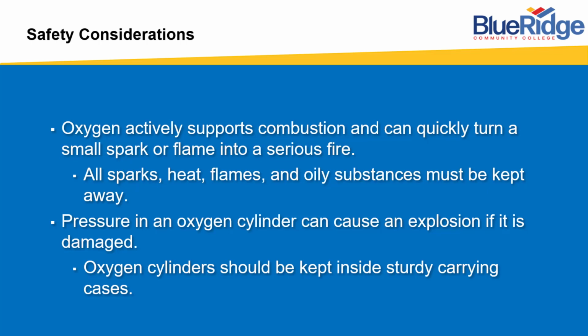High pressure in an oxygen cylinder can cause an explosion, as I've just mentioned, if the cylinder is damaged. Oxygen cylinders should be kept in sturdy carrying cases and should be handled with care to guard against any damage or dropping. Storing these cylinders at your department or base or headquarters, they should be in locked containment cages, and we typically, just for tracking purposes, usually separate them into full categories and empty categories.